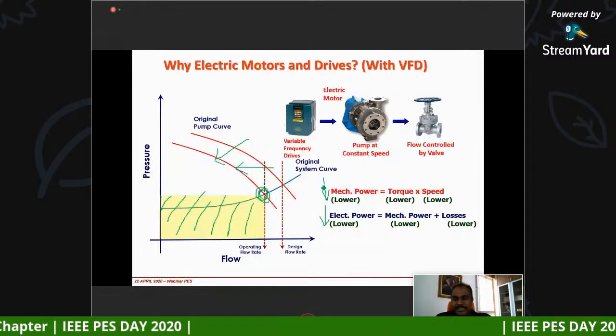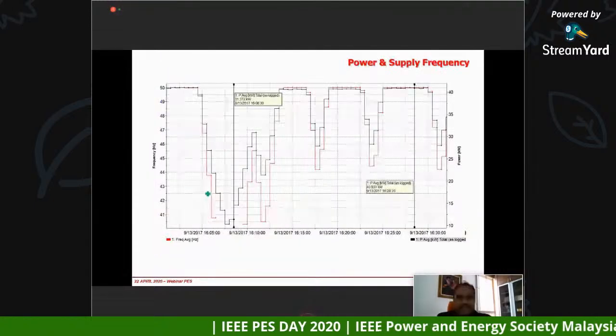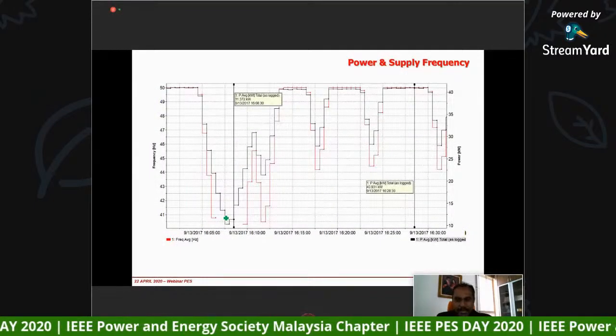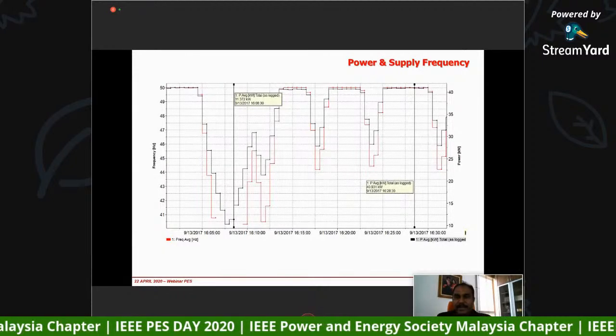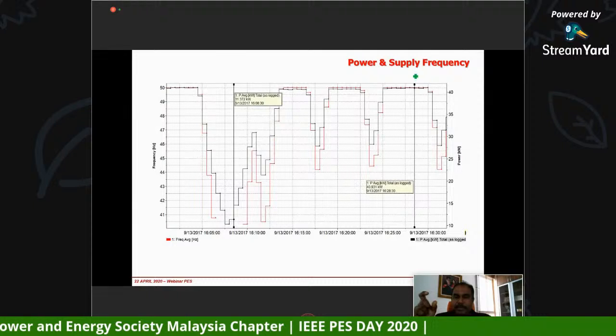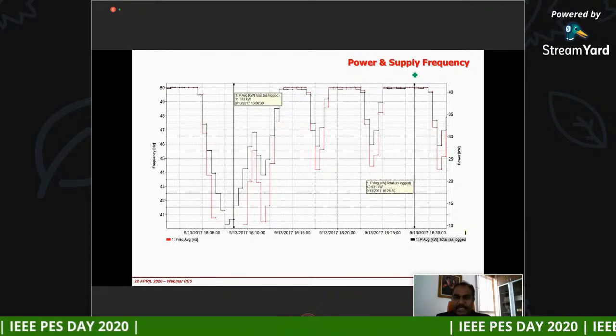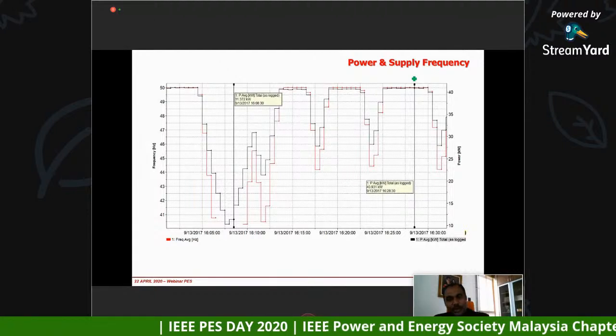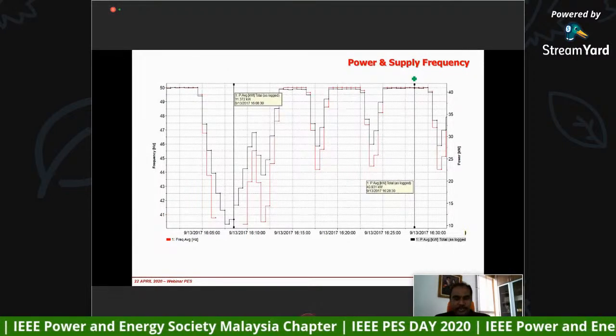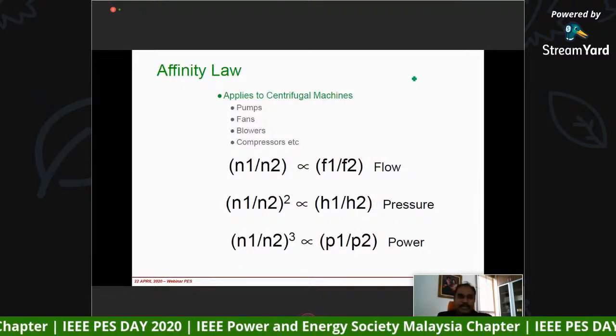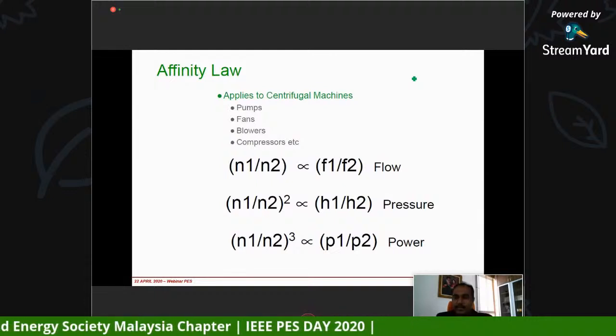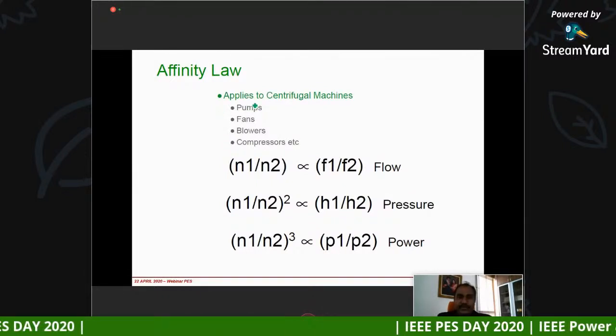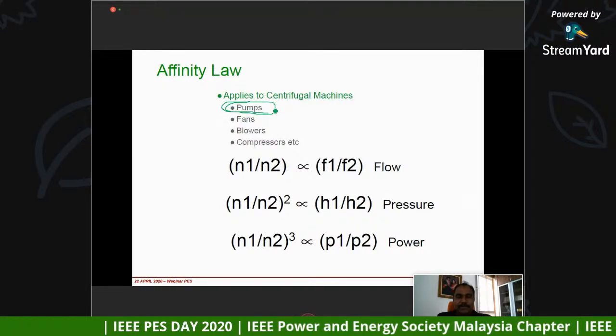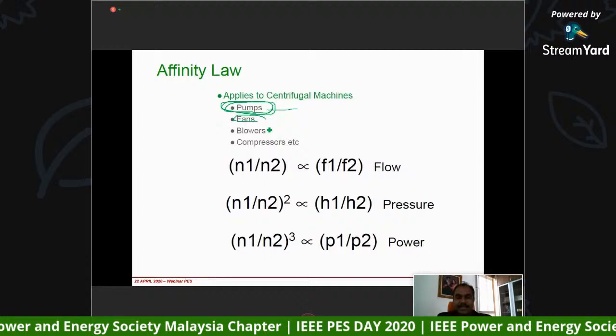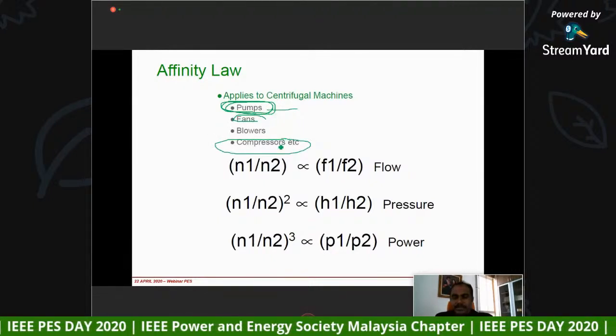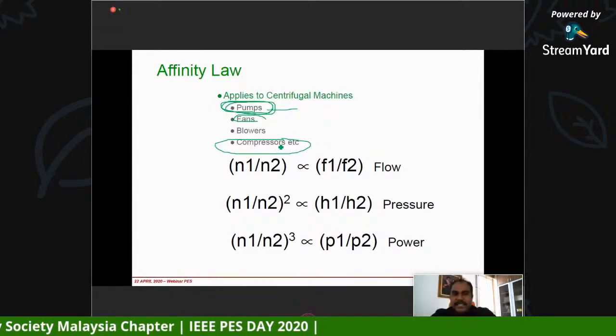Okay, right. So as everyone will know, as far as the induction motor is concerned, every time we change the supply frequency, we change the speed of the induction motor. Every time we change the speed, the frequency or the speed, we see that power is also proportionally reduced. Okay. In fact, I think this is also the mechanical law, the pump law, affinity law. It always applies to most of the systems. In Malaysia, almost 70 to 75% of our load is a pump load, followed by fan, followed by compressor. So that means all of them will actually comply with this affinity law, because all of them are centrifugal machines.